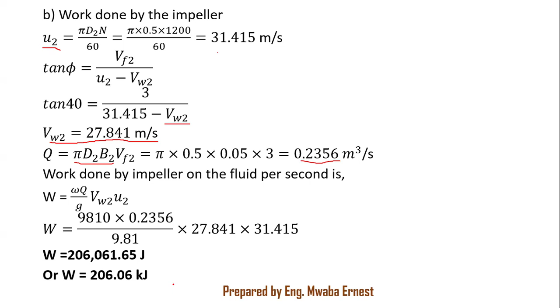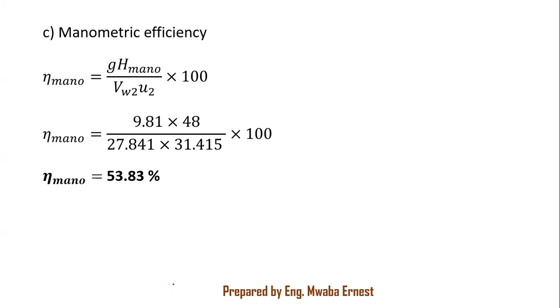Manometric efficiency is g times manometric head over VW2 U2, then of course you multiply by 100. So we substitute g, 9.81, times our manometric head, 48, divided by VW2, which is 27.841, times U2, which is 31.415. Again, multiply by 100. You get 53.83%.